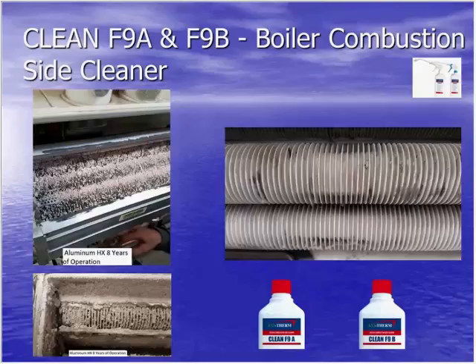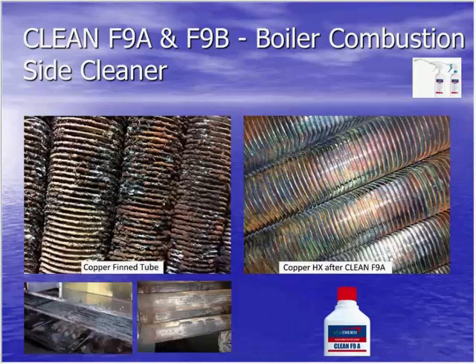This next picture is a copper finned tube boiler. This was cleaned by a contractor who works for a property management company. As you can see, it was thoroughly clogged to the point where it could not really pass through the copper fins, to the point that, in the picture in the bottom center there, those stainless steel burners simply became roasted and had to be replaced.